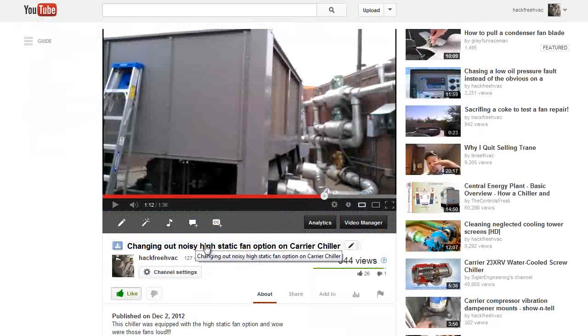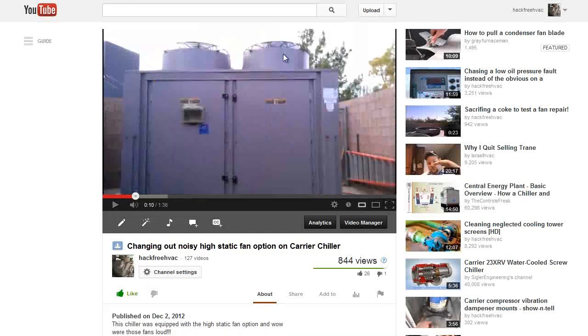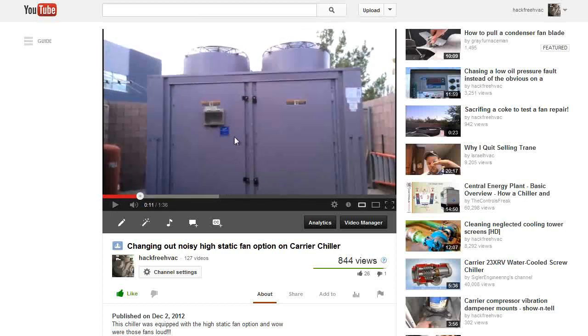Here's one of the videos these guys are trolling. This is the one from last year where I changed the fans — it was still hot when I did this. This unit came with the high static fan option, and they were loud — you had to use earplugs to stand next to them. This is not the standard option; it's something that's specially ordered with the unit. It was not needed in this area to have the high static fan option.